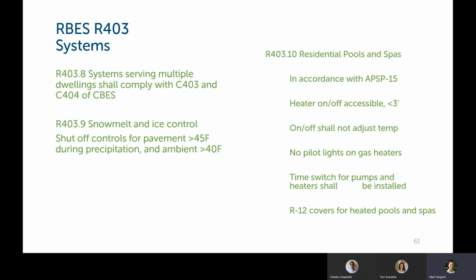There's pools and spas. The on-off heater switch has to be accessible and less than 3 feet away from the heater. We have to design residential pool and spa heaters in accordance with APSP 15. The on-off switch cannot adjust the temperature. No pilot lights on the gas heaters. Also, the time switch for pumps and heaters shall be installed. And R12 insulated covers for heated pools and spas are required.